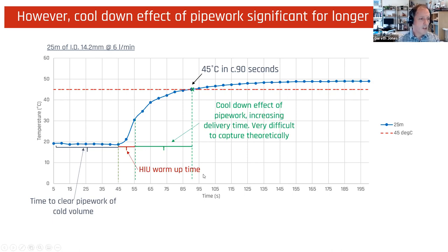again, you've got the same HIU warm-up time. The time to clear pipework of cold volumes is a lot longer. But the thing that a lot of people, again, do not take into consideration is this big cool-down effect of the pipework, which really increases delivery time. It's quite difficult to capture theoretically. So in this instance, 14.2 mil, which is similar to the 15 mil you'd see with copper, you're talking about 45 degrees in 90 seconds. So double the time that is actually a requirement under CP1 2020.